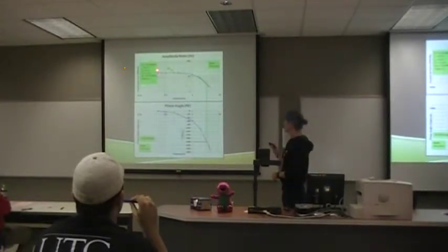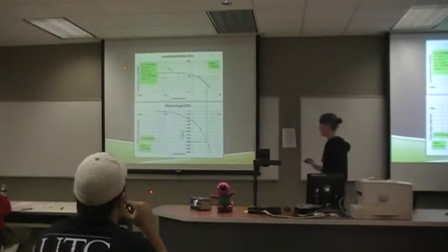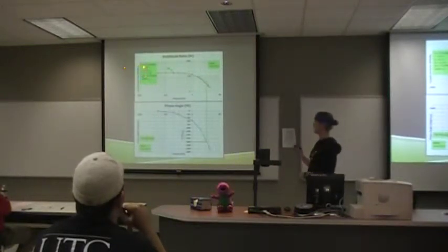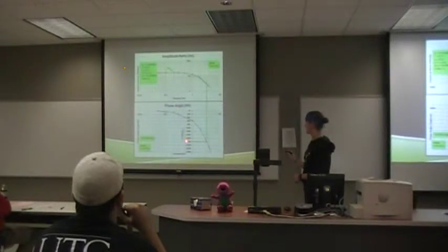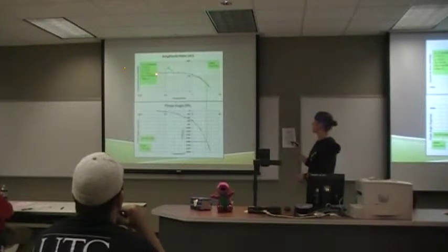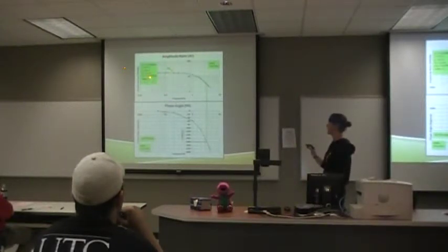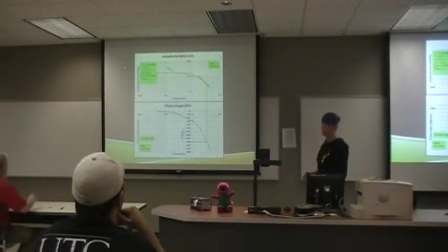K turned out to be about 17.6, tau is 0.17, and T naught is 0.3. This is for the 50 to 75% range. And then FU and KCU were found by corresponding the phase angle of -180, and then going up here and finding the frequency. The frequency is 3.2 hertz, and then the ultimate controller gain was 0.4 RPM per percent.